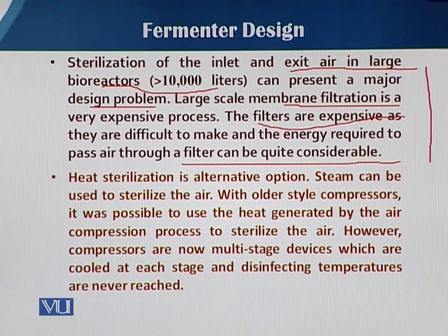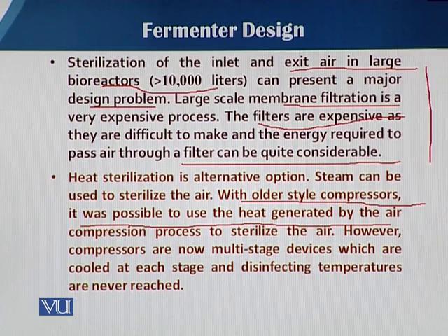As we know, heat sterilization is an alternative option. Apart from the filter system, a heat sterilization system is also used. So steam can be used to sterilize the air. In older style compressors, it was possible to use heat generated by the air compression process to sterilize the air, because when the compressor compresses the air, heat is also produced.